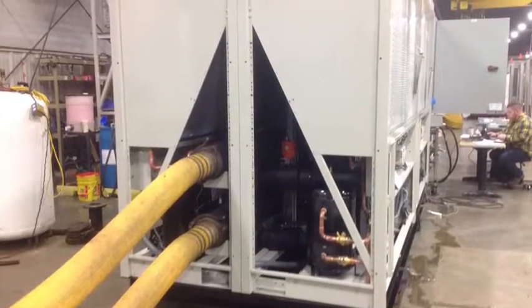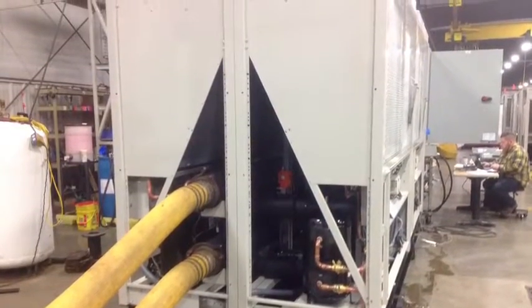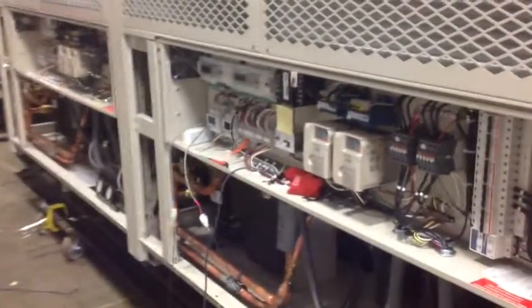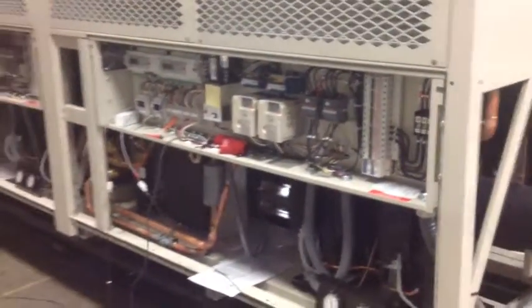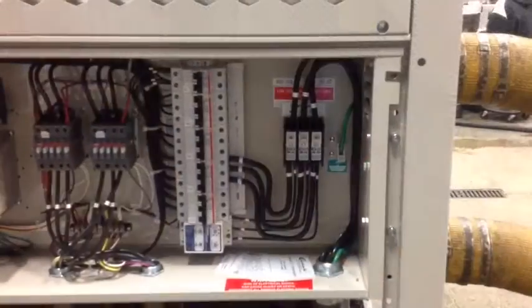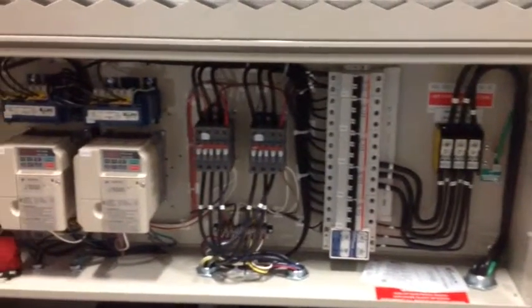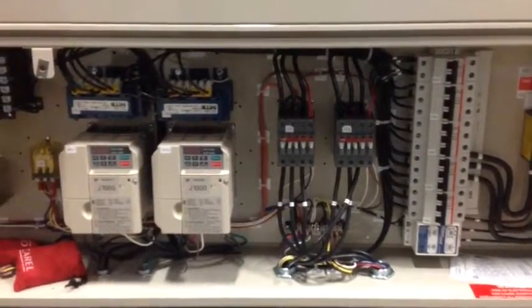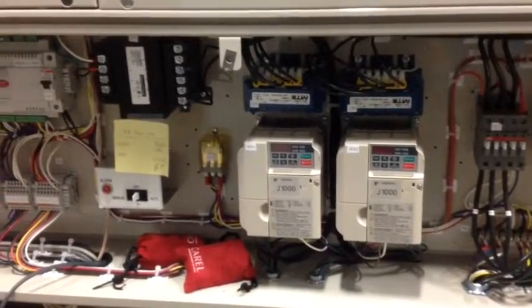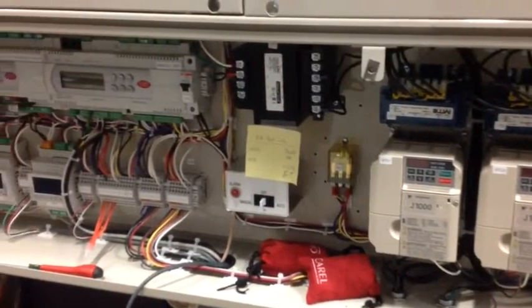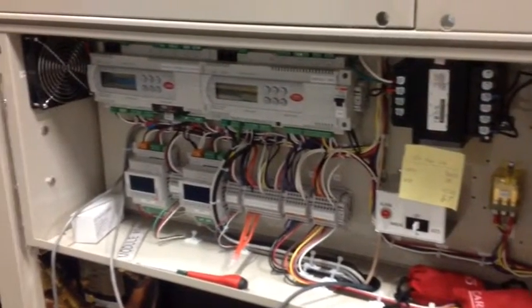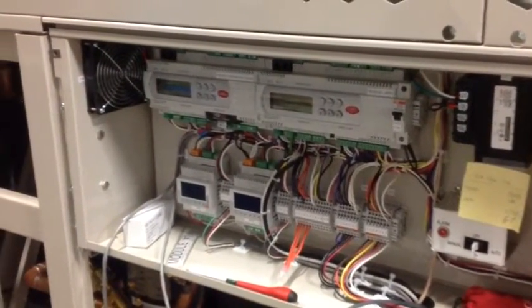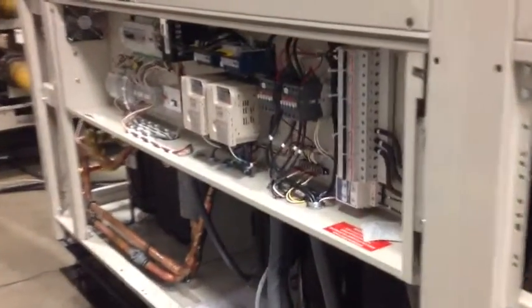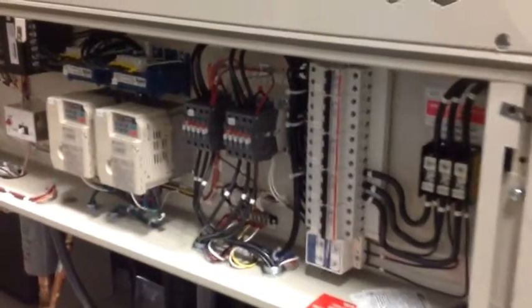Now let's take a tour of the mechanical modules. You can see the entering and leaving chilled water connection. And now moving around to the building side of the array, we'll see the master mechanical module. We'll pan right to left, but we'll come back with a little bit more time to review this component by component. You'll notice this control panel has 2 Carel controllers at the top. And as we pan to the left, this slave module only has 1. We'll explain that difference in just a minute.